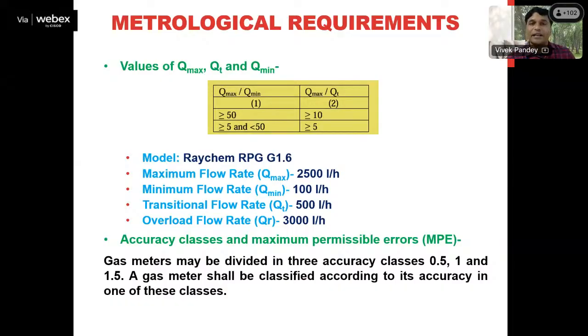In our example, the maximum flow rate specified by a manufacturer is 2500 liters per hour, the minimum flow rate is 100 liters per hour, and the transitional flow rate is 500 liters per hour. Suppose we want to check whether these 3 flow rates are correct. In our rule, a table is specified for checking this, and you can see that if the ratio of Q maximum to Q minimum is greater than or equal to 50, then the ratio of maximum flow rate to transitional flow rate should also be greater than or equal to 10. If this condition is followed, then it is correct.